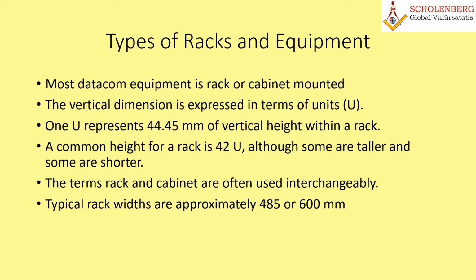So if you see what racks are, most datacom equipment is either rack or cabinet mounted. The vertical dimensions of a rack or cabinet are expressed in U. One U is equal to 44.45 millimeters of vertical height within the rack. A common height of a rack is 42U, that is 42 multiplied by 44.45. That's the common height found in the industry. Some racks are taller and some shorter, but you'll find 90% of racks are of similar height.